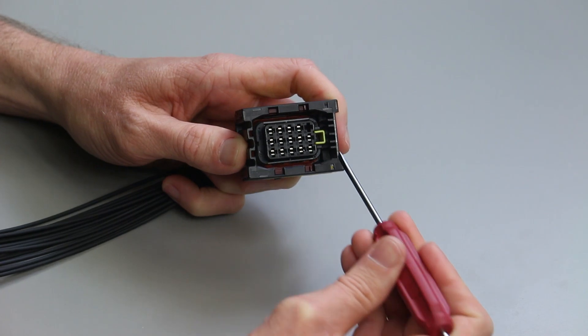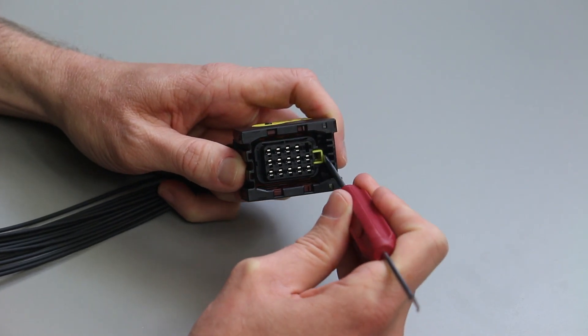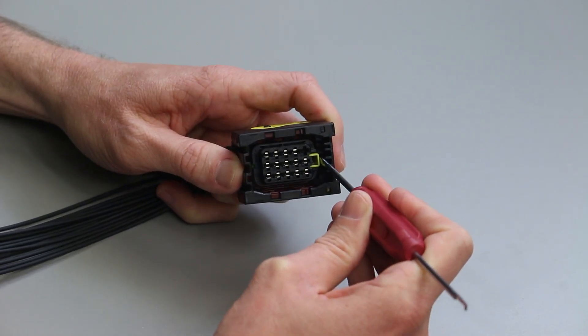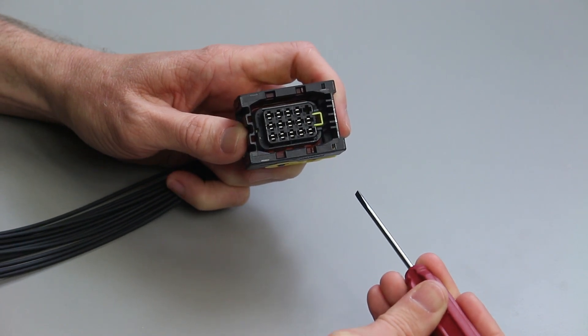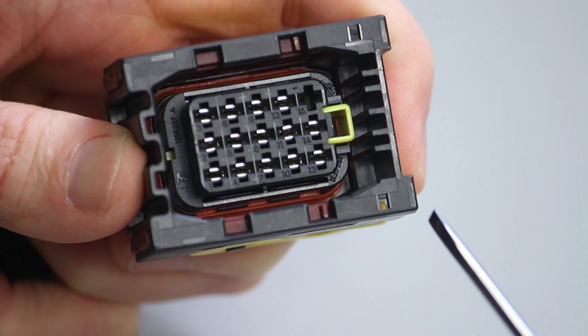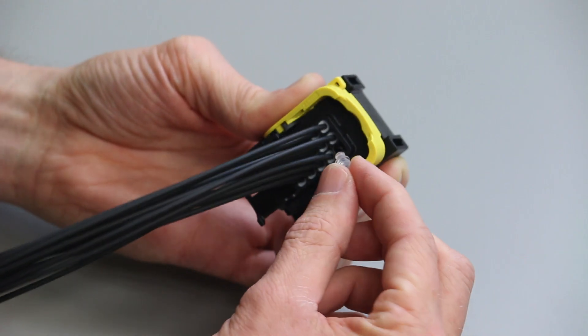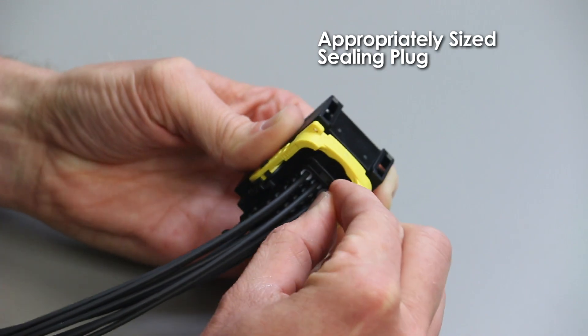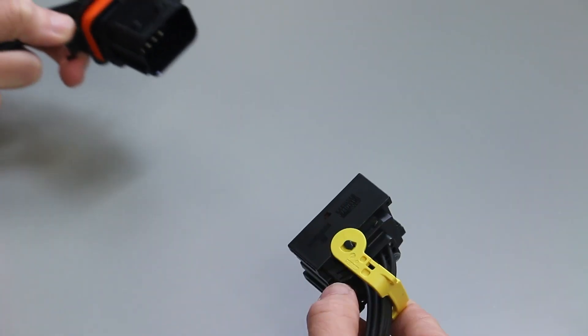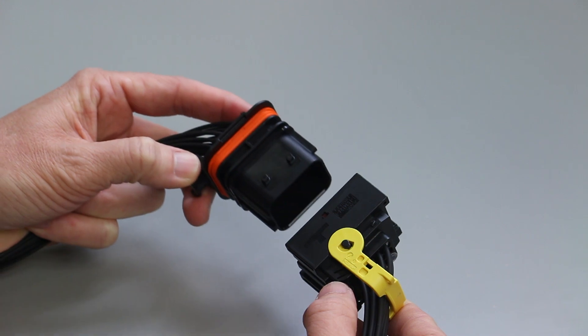After all the contacts have been inserted, slide the integrated secondary lock into the locked position with the DT-RT1 removal tool or a screwdriver. Please note that if you have open cavities, they will need to be filled with appropriately sized sealing plugs. Repeat this process for both connector halves.